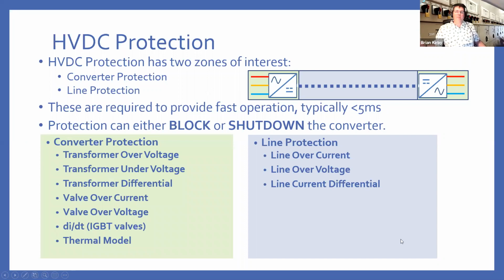Okay, so if we look at protection on HVDC, we have two real zones of interest. We have protection within the converter and protection on the line. In the converter, we have the transformer protection, which is effectively AC protection on the transformers from the AC to the DC side. And we have valve protection, which is protection of the power electronics, including the thermal model. On the line, we're just purely protecting the line itself, DC, and we have two protection operations we can take. We can either block or we can shut down. Typically, if the fault's on the line, you can block the line but keep your converters energized. But if the fault's on your AC side, you generally have to shut down because you don't want to propagate faults onto the AC network.